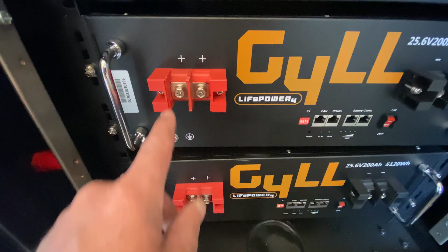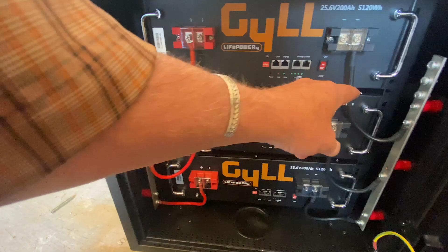Okay, the next step will be to wire from the battery to the bus bar. We'll go from each one of these points to the threaded connection here, and then eventually take these and go with 4-gauge wire, 4-aught, that will hook to the charge controller and the inverter.